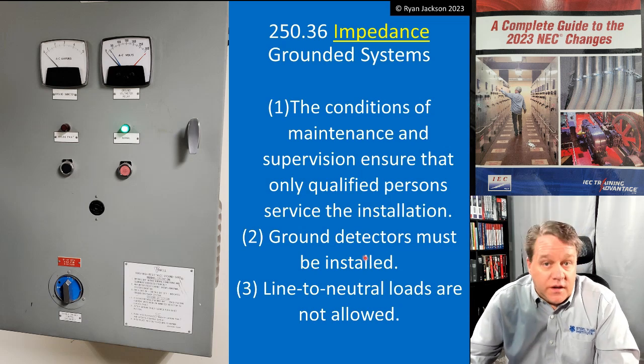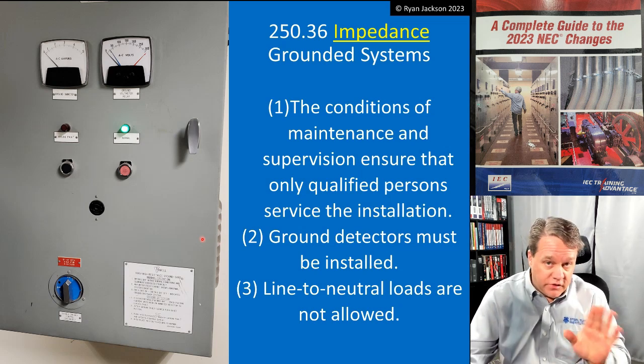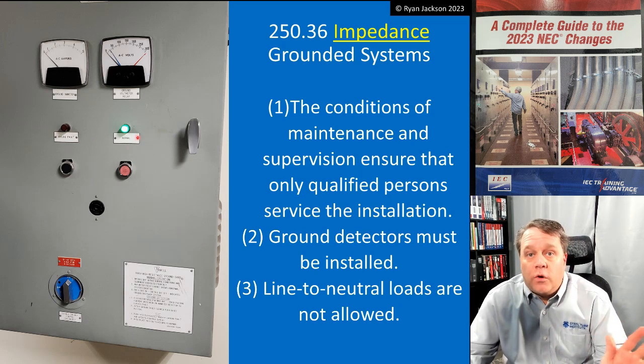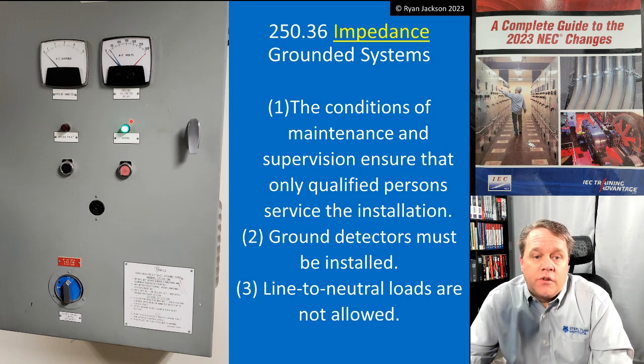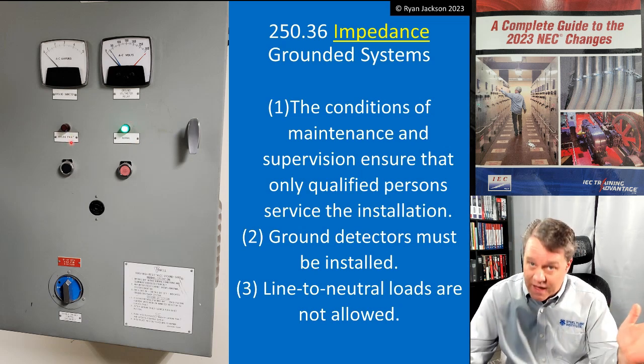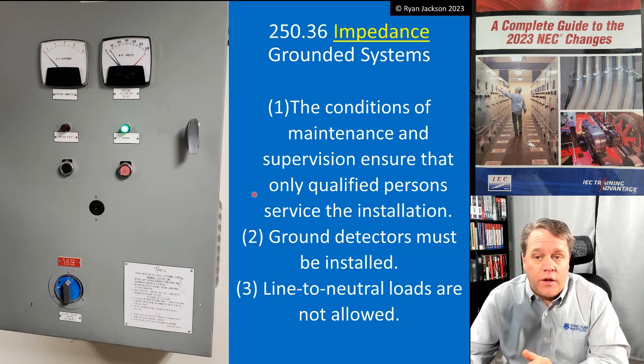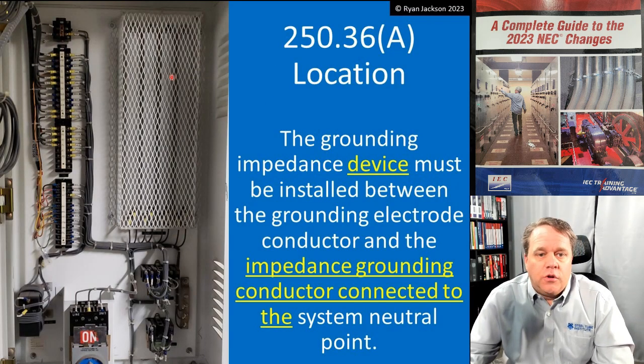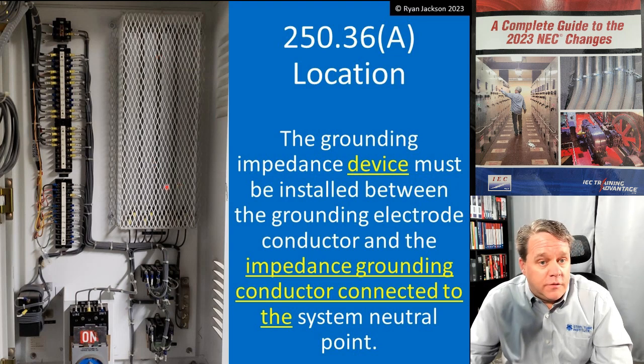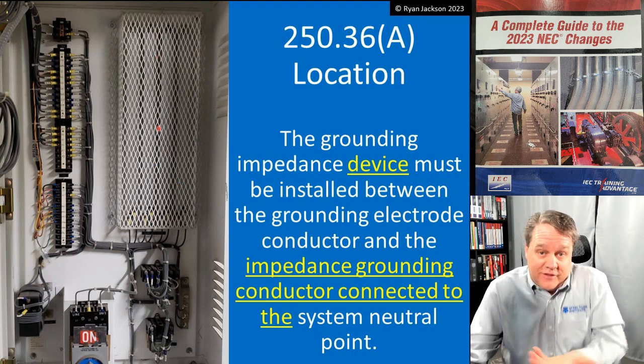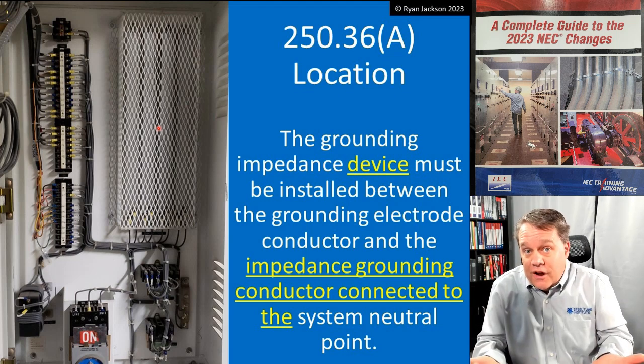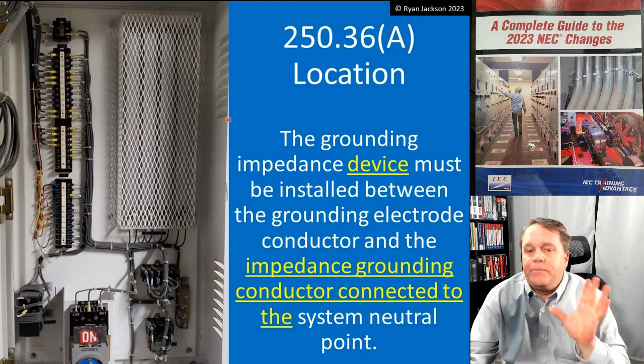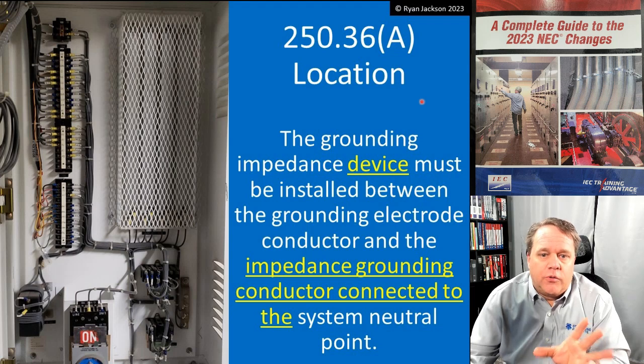Here is an example of an impedance grounded system - this is a small one. This is the ground detection system right here: the green light is on, everything is working perfectly. If that shuts off or turns red, and the light on the left turns on, that means we have a ground fault and we need to figure out what's going on. If I open this piece of equipment, it looks like this - that is the actual resistor. A slang term for this is a 'toaster,' because when you look at it it's just like a toaster - a toaster is just a big old resistor. Same thing here.